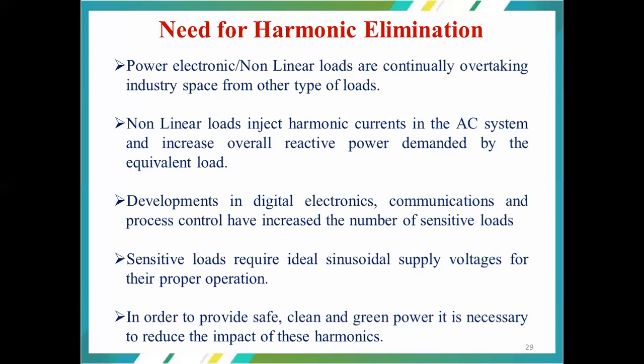So the need for harmonic elimination is that power electronic or nonlinear loads are continuously overtaking industry space from other types of loads. As I already mentioned, once upon a time the induction motor alone was the load, also called the workhorse of the industries. In recent times that is not the case. Even when we feed the induction motor, we feed it through power electronic converters, and we maximize the operating efficiency.